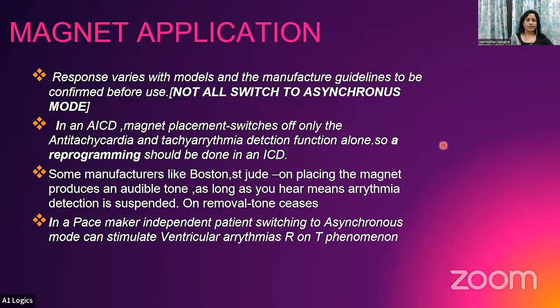Certain manufacturers, like Boston and St. Jude, also have the advantage that you can hear an audible tone when it changes to the asynchronous mode. From that you can identify it is in the asynchronous mode, as long as the beep sound is heard. On removal, converting it to the previous rhythm, the tone will cease. So this is an advantage. From the sound you can make sure that it is still in the asynchronous mode, especially during the intraoperative period.